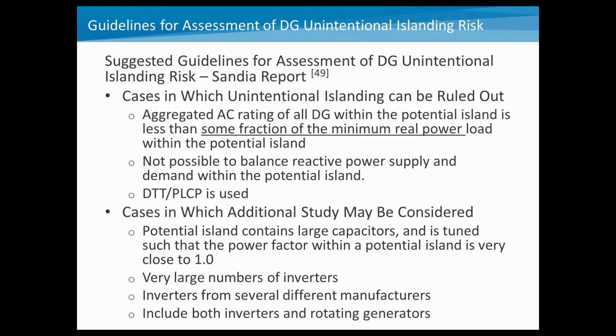Additionally, they said you should consider a closer study if the potential island contains large capacitors and is tuned to a power factor at which you could maintain the real and reactive power balance inside that island. If you have a very large number of inverters, say 100 or 1,000 inverters inside a particular area, that may warrant additional consideration. Also, if inverters are from a variety of different manufacturers, often you don't know exactly what anti-islanding technique they're using in their systems, though you can ask the manufacturer to provide more information. And if potential islands may include inverters and rotating synchronous generators, you want to take a closer look, because the rotating generators could potentially trick the inverters into staying on longer than you would think. But again, these are guidelines to help someone assess the actual probability of islanding.